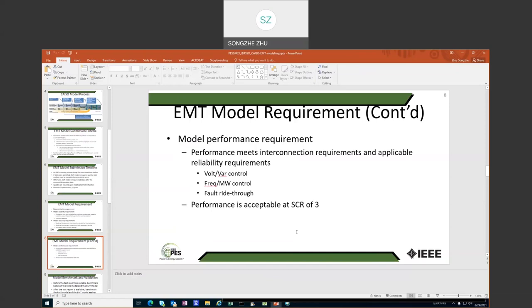And we also require that the performance must be acceptable at a short circuit ratio of 3. This is based on the forecast short circuit ratio in our system. So right now, in the California ISO, we still have a decent SCR, but as more and more IBRs replace the synchronous generators, we have observed that SCR would get down to almost 3. So that's why we require an SCR of 3 for the model validation.